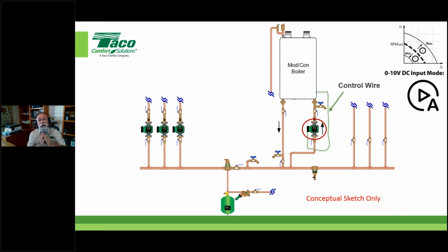So if it sees a delta T that starts to widen, that's its signal to say, hey, if it goes beyond what you want it to, let's get some more pumping going on, and pull that energy out of the heat exchanger and send it into the secondary, and tighten up that delta T. On the other side, if we see delta T's that are too tight, tighter than they should be, then let's slow that circulator down and get back into a lower return temperature to stop that water from coming across these two T's I spoke about earlier.